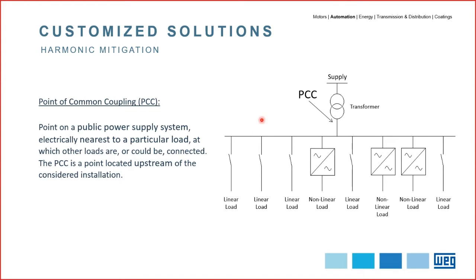In this example, the PCC is in the secondary busbar of the transformer. It means that the harmonic limits established in the IEEE 519 should be verified at this point and not necessarily at the input of the VSDs connected to the busbar, like for example here. However, if the PCC is to be considered at the input of the VSD, WEG is also able to provide solutions to reach the required harmonic levels for current. On the other hand, compliance with voltage harmonic limits depends on other system characteristics, such as the impedance, presence of other nonlinear loads, and so on.